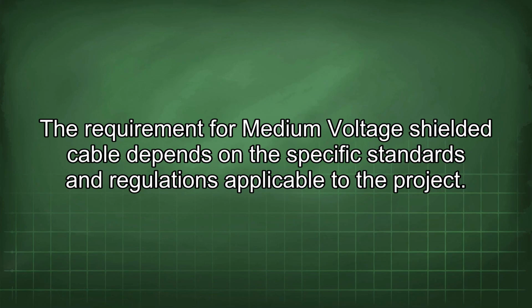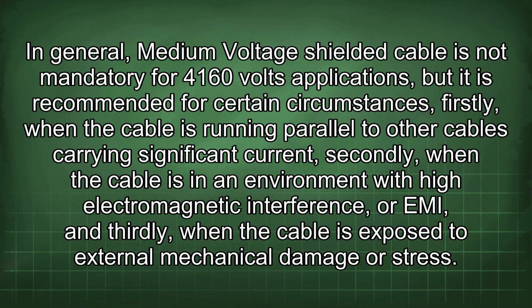The requirement for medium voltage shielded cable depends on the specific standards and regulations applicable to the project. In general, medium voltage shielded cable is not mandatory for 4160 volts applications, but it is recommended for certain circumstances. Firstly, when the cable is running parallel to other cables carrying significant current. Secondly, when the cable is in an environment with high electromagnetic interference, or EMI. And thirdly, when the cable is exposed to external mechanical damage or stress.